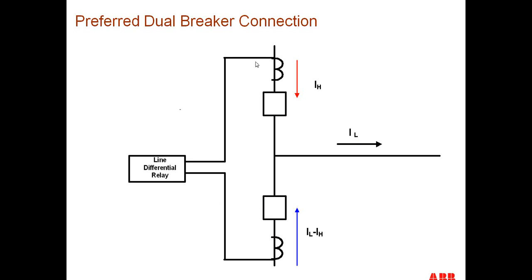So our preferred way of doing this is to hook the two CTs up coming into separate inputs into the relay. And so we now have all the information about each of the breakers, all the information about the CTs. If one CT happens to be putting out no current because it's saturated or because it's open circuited, we know that at the relay now. And now we can, if we want, have a breaker failure relay built into the differential relay, and because the currents are separate, we know exactly what the currents are through that one particular breaker if the breaker happens to fail and not open properly.